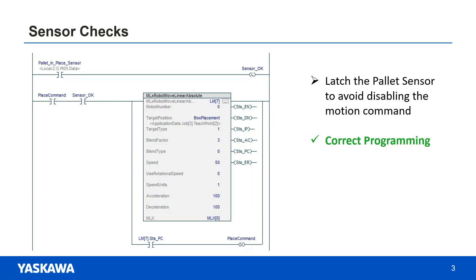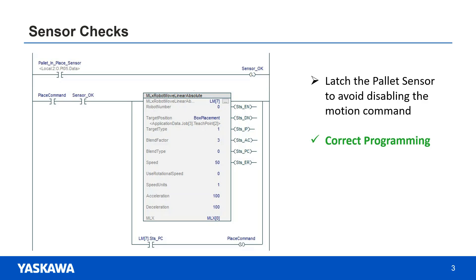The solution to this problem is to latch the sensor input when it is first detected and use the latch signal as a condition to command the motion. You will also need to unlatch this tag after it's been off for a certain period, but make sure the motion command is not being executed at that time.